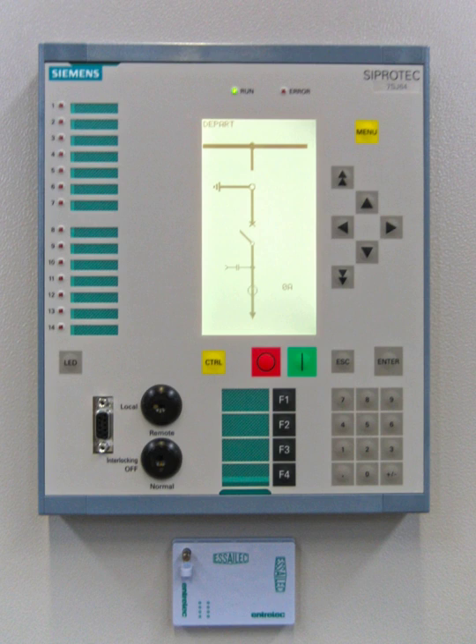Reliability. Devices must function consistently when fault conditions occur, regardless of possibly being idle for months or years. Without this reliability, systems may cause costly damages. Selectivity. Devices must avoid unwarranted, false trips. Speed. Devices must function quickly to reduce equipment damage and fault duration, with only very precise intentional time delays. Economy. Devices must provide maximum protection at minimum cost. Simplicity. Devices must minimize protection circuitry and equipment.